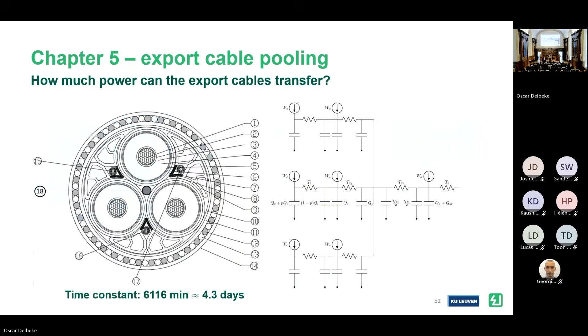So big thermal inertia. Then I look at the cable's temperature throughout the year. What I see is that over a period of 2 years, I see my complementarity figures return. I see that in winter, these cables are used very well, close to their limits. They transfer a lot of power. But during summer, there's much more margin to transfer more power, which means that these cables could transfer more power exactly when solar power could produce most electricity. So this is a big promise.